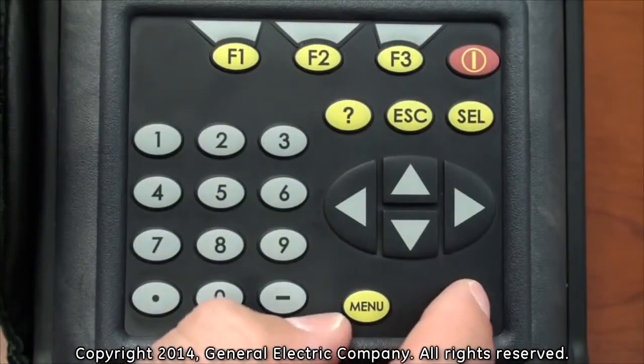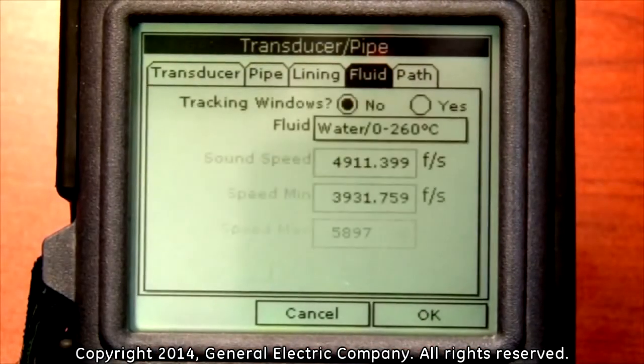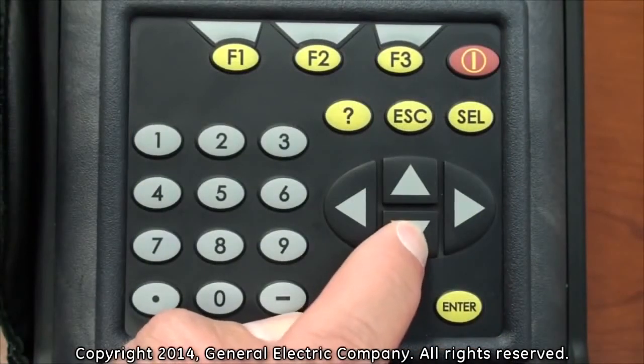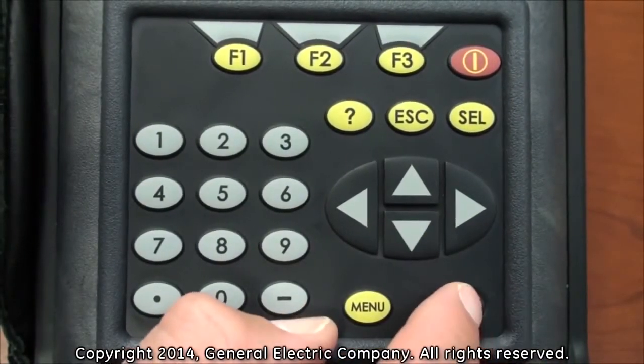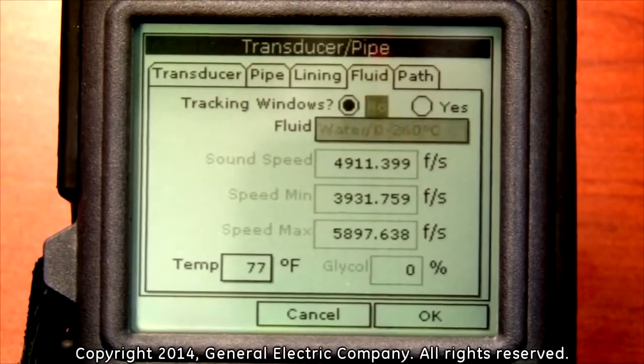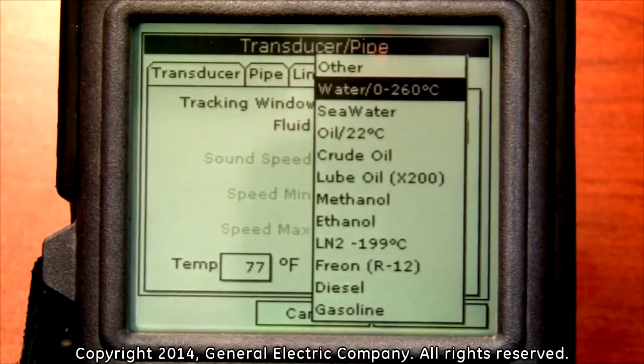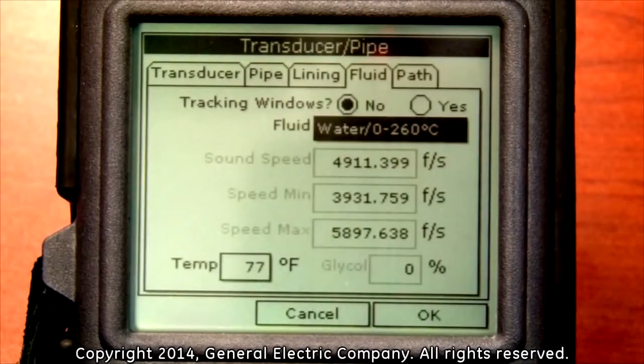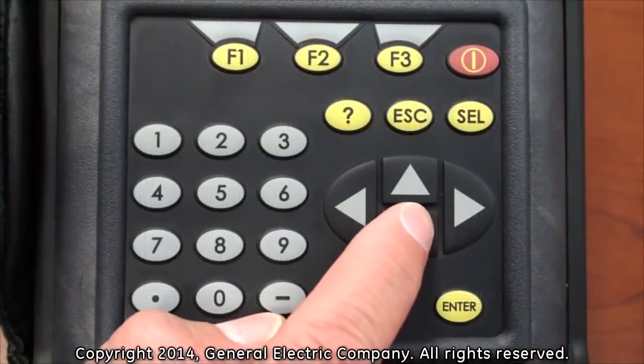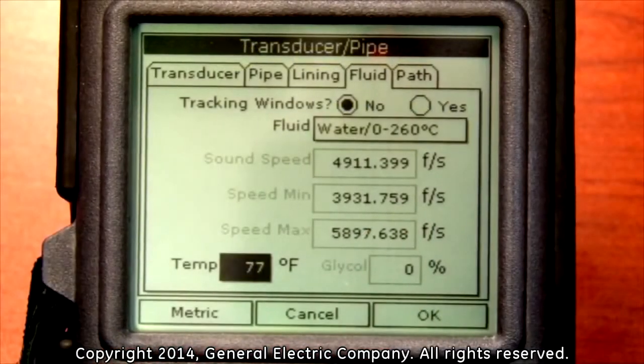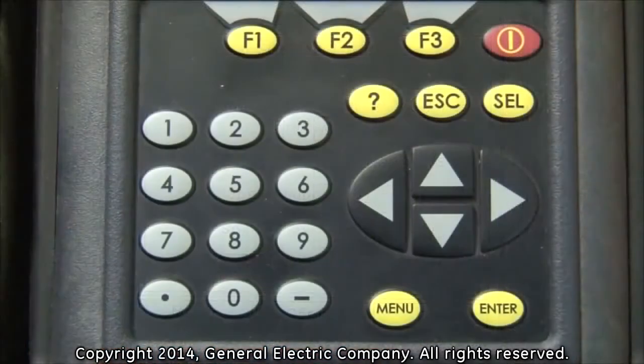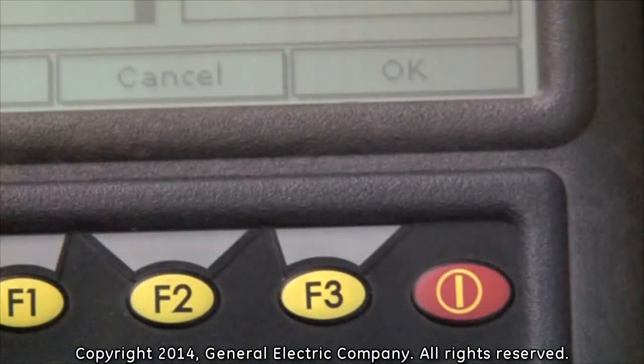Press the Enter button to open the fluid parameter menu window. Press the down arrow key on the keypad to highlight the fluid selection field and press the Enter button to view the available options. If the fluid you are looking for is not in the options, choose Other. Then you will have to manually program the fluid speed. If you choose water for your fluid, you will need to program the temperature of the water by using the down arrow key and pressing Enter on the temperature input field. When the temperature is set, press the Enter button. Press the F3 button, which corresponds to the OK selection on the bottom right of the display screen.